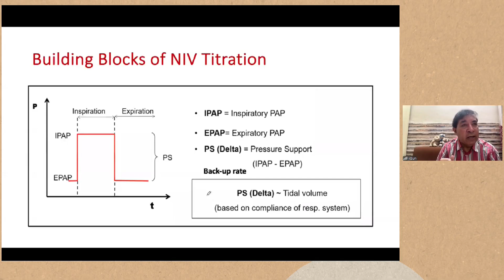To address this, advanced settings are added to these bilevel devices. So bilevel ventilatory supports have advanced settings. What are these? These are trigger sensitivity, the rise time, the inspiratory time, and the cycle sensitivity. All of these can be manipulated for different types of lung diseases like OHS, overlap syndrome, COPD, and neuromuscular disorders. The tidal volume here is a function of two factors. One is the difference between the IPAP and EPAP, which is the pressure support, and the other factor is the inspiratory time. Suppose you cannot increase the pressure support and you want to enhance tidal volume, then you can increase the inspiratory time.